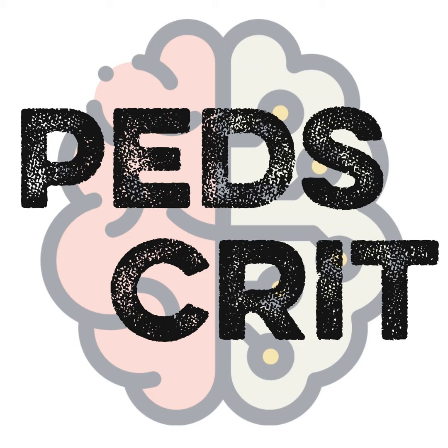The next one, the one that we use most commonly in the unit, is flow trigger. The ventilator sees the circuit as a closed circuit. No air should be leaving the circuit at any point. And therefore, if all of a sudden flow is moving away from the ventilator, then that must mean the patient is trying to take a breath, in the ventilator's view. The only thing the ventilator can see is that little pipe coming out. Flow's leaving, it must be going into the patient, therefore I need to give a breath. Most of the time, that benefits us really well. Sometimes that can be a problem. But nonetheless, that's our flow trigger.